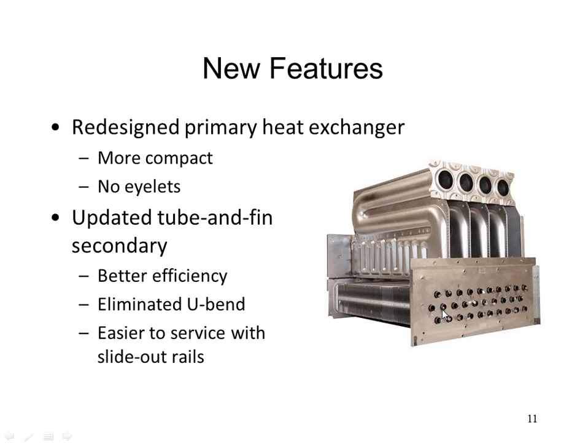If you were to pull that tab out, you'd get a corkscrewed piece of metal called a turbulator. And that guy's job in life is to basically cause the gas that's coming through those tubes to get mixed up. So the gas has to come into contact with the outside of its tube, which gives us a little bit more efficiency. I guess at this point we're fighting for 0.1% of efficiency, because once you get up to a 98% efficient furnace, there's not a lot left to squeeze out of this thing. But that's some of the stuff they're doing to make that happen.